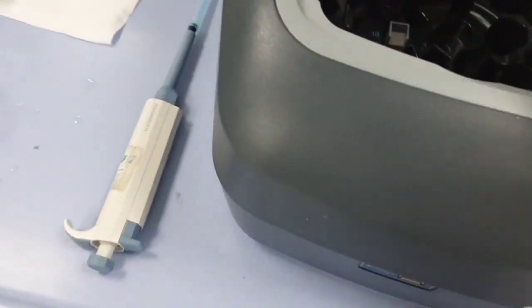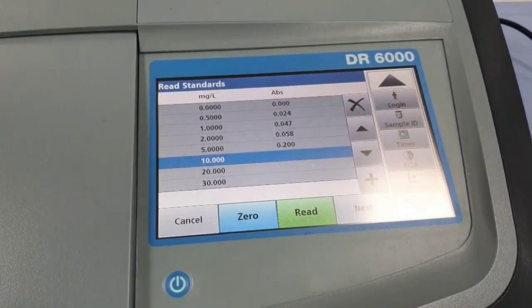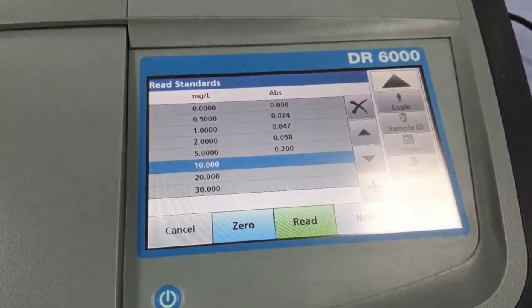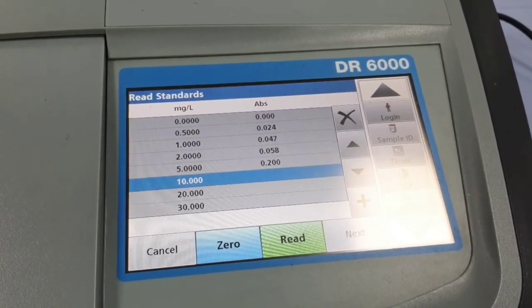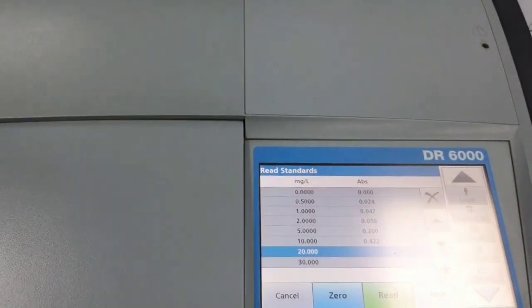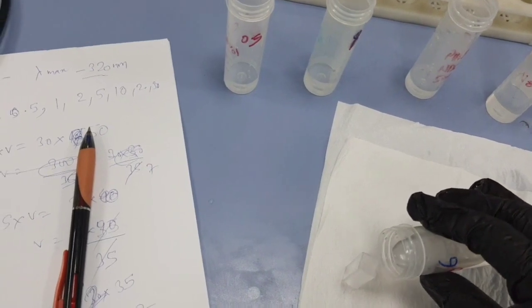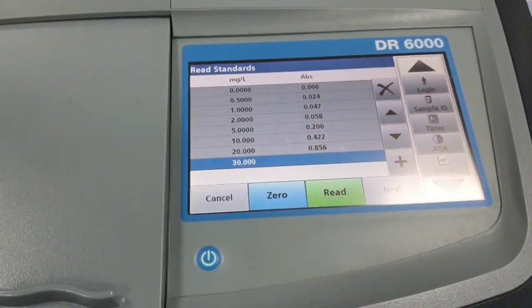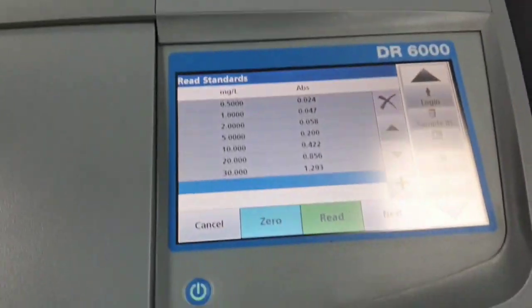If you see, 1 ppm is 0.047, so 5 ppm is almost 5 times that. Now we will check the absorbance of 10 ppm. You can see it's almost double that of 5 ppm. Then 20 ppm is also more than 10 ppm, almost double. Now we will take the absorbance of 30 ppm, which is more than the 20 ppm.